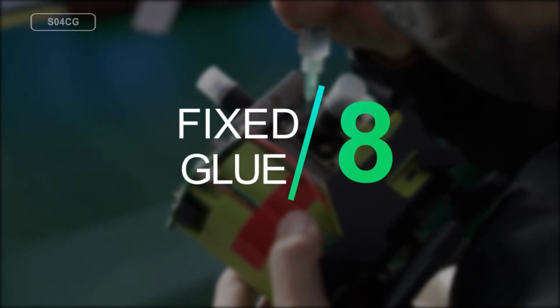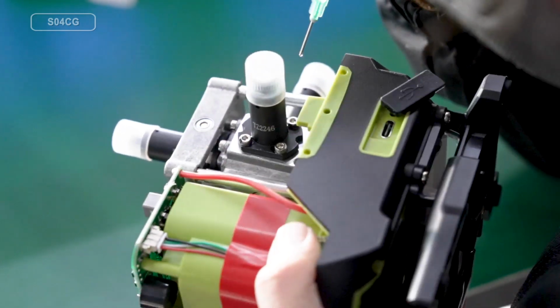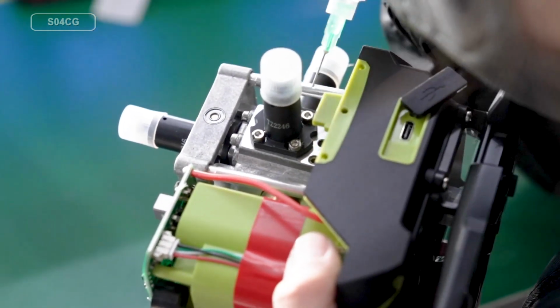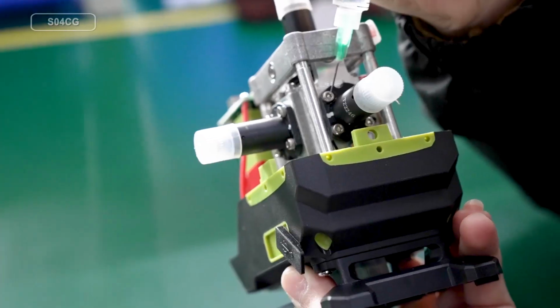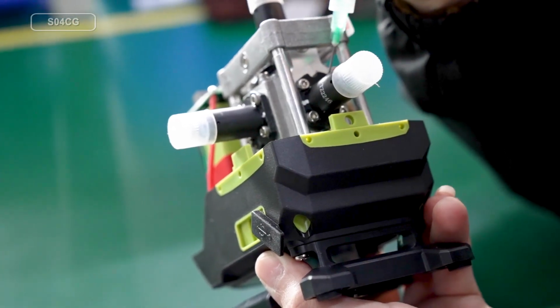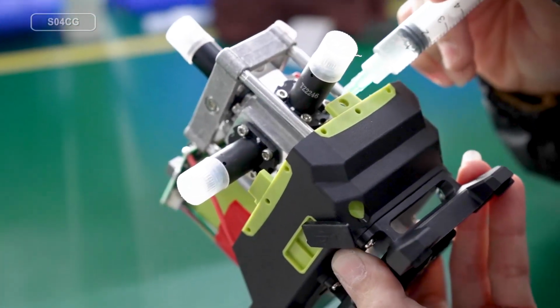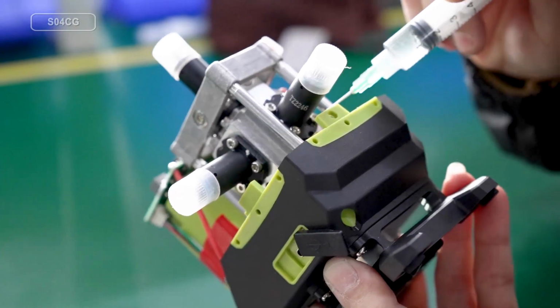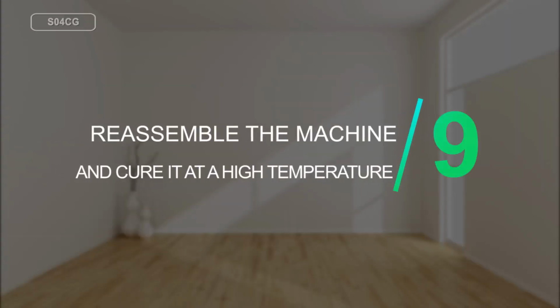Fixed glue. Fixing the module screws. Fill screw glue with needle cylinder. Align the needle at the interface between the module screws and the module frame plane, and then do the dispensing. Reassemble the machine and cure it at a high temperature. It can be cured for 6 hours at room temperature.